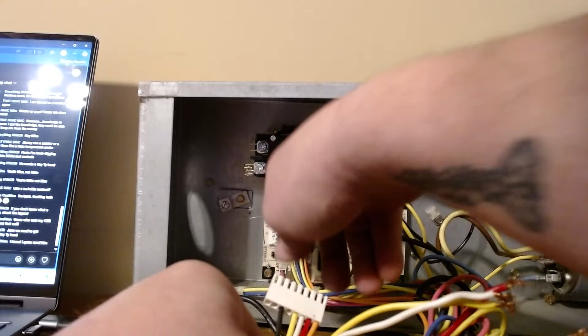So I'm gonna pull this pin out, and as everyone can see, you have O, R, W, Y, then a space and C. So O, R, W, Y and a space for C. If you ever come across one of these where your common wire, your black wire, is directly next to yellow, so the wire is not sitting here, it's right next to it, there's not a gap there, you need to get that pin puller, pull it out and move it over a spot.